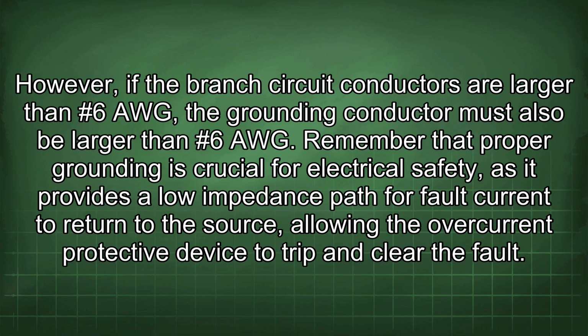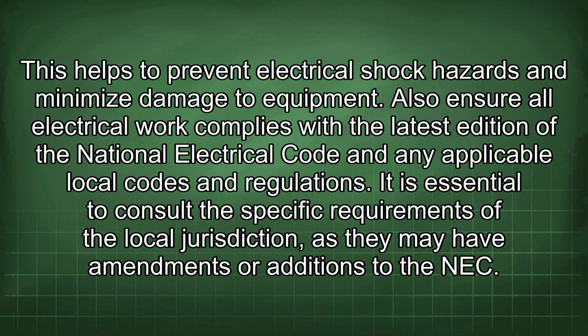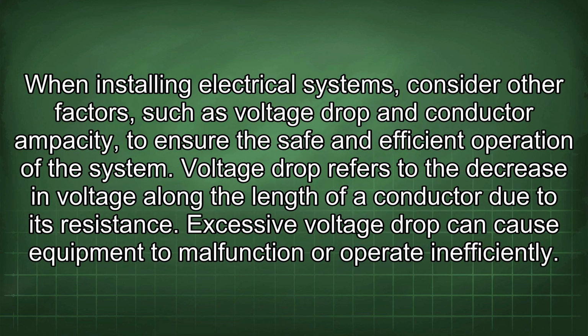Remember that proper grounding is crucial for electrical safety, as it provides a low impedance path for fault current to return to the source, allowing the overcurrent protective device to trip and clear the fault. This helps to prevent electrical shock hazards and minimize damage to equipment. Also ensure all electrical work complies with the latest edition of the National Electrical Code and any applicable local codes and regulations. It is essential to consult the specific requirements of the local jurisdiction, as they may have amendments or additions to the NEC. When installing electrical systems, consider other factors such as voltage drop and conductor ampacity to ensure the safe and efficient operation of the system.